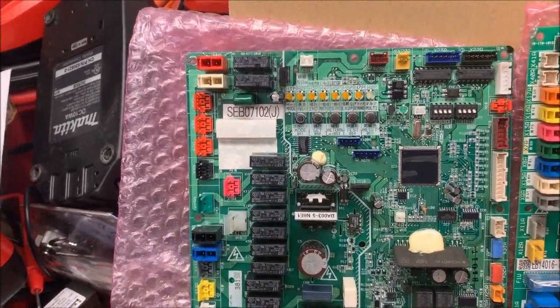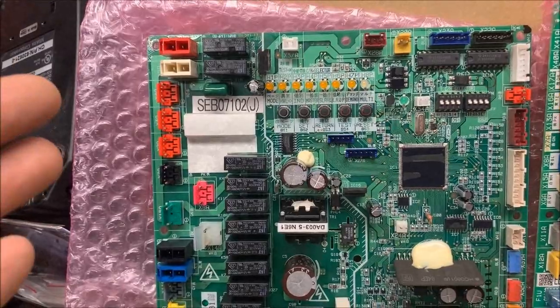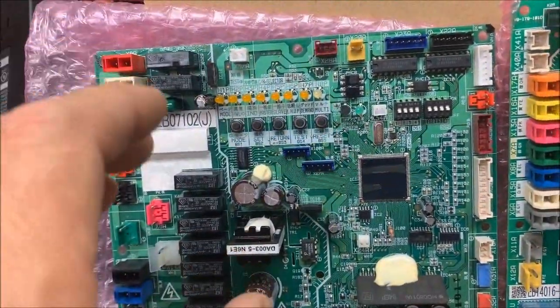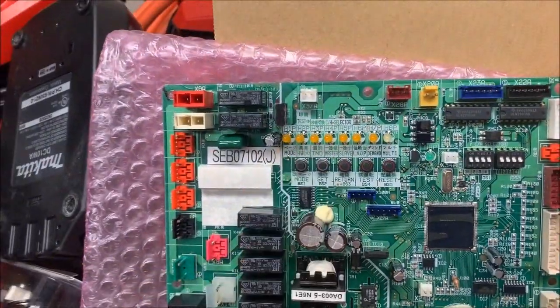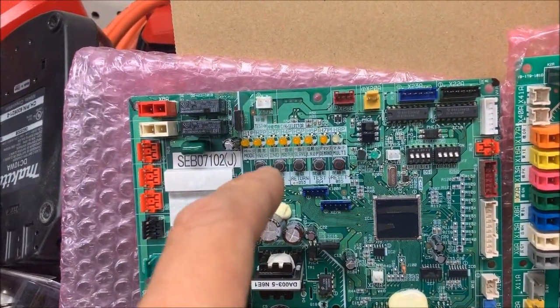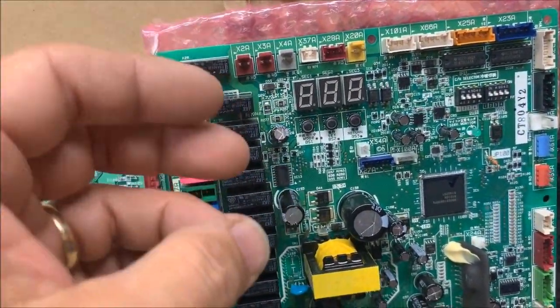Once you do that, you can lock out that module so the other module will run — that gets you by in emergency operation until you can make the repair. On VRV4, it's a little different because here you press BS1 to go into monitor mode. When you're done checking everything, you just press that button and it goes back to normal. On VRV3, pressing 14 gives you the latest error, 15 gives you the error before that, and 16 gives you two previous errors before the current. On VRV4, it's 17, 18, and 19 — 17 being the latest, 18 being previous, 19 being two previous.